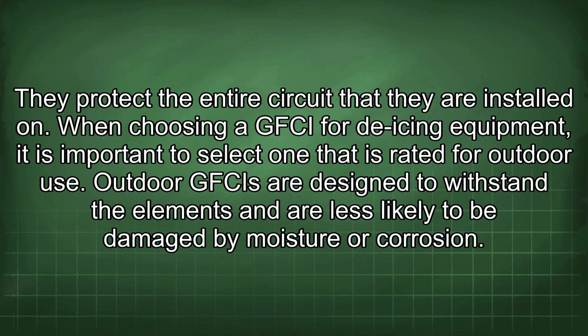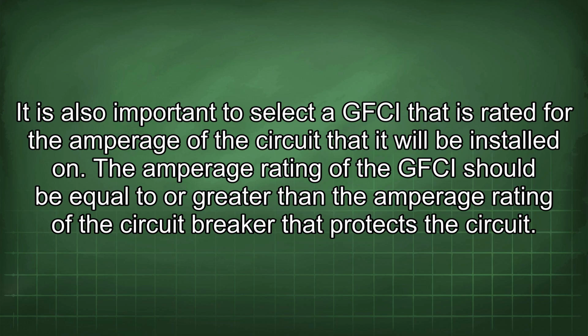When choosing a GFCI for de-icing equipment, it is important to select one that is rated for outdoor use. Outdoor GFCIs are designed to withstand the elements and are less likely to be damaged by moisture or corrosion. It is also important to select a GFCI that is rated for the amperage of the circuit that it will be installed on. The amperage rating of the GFCI should be equal to or greater than the amperage rating of the circuit breaker that protects the circuit.